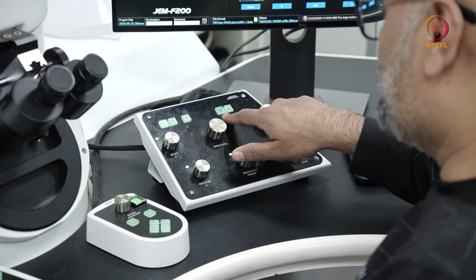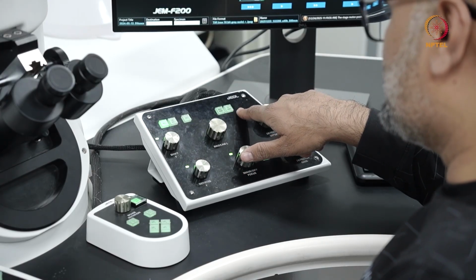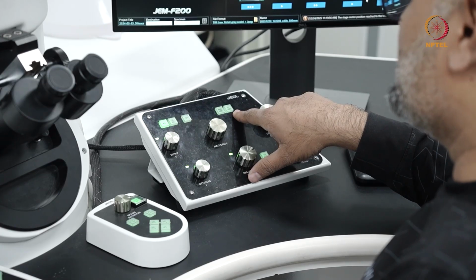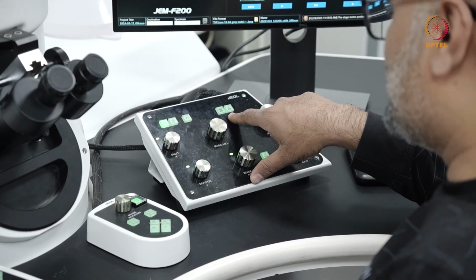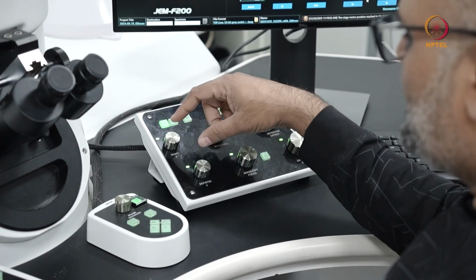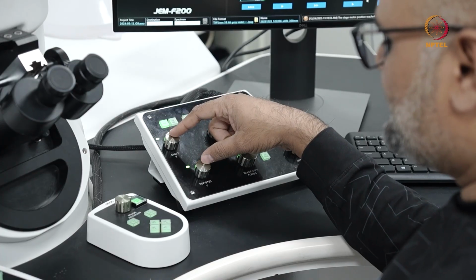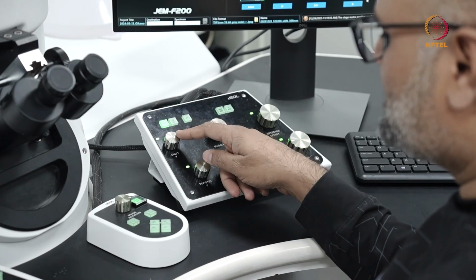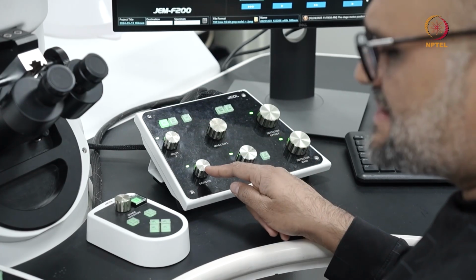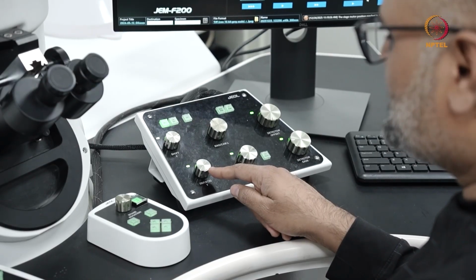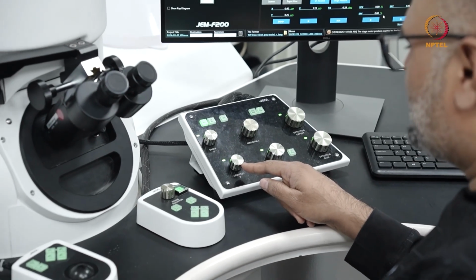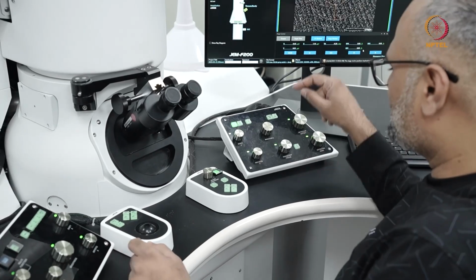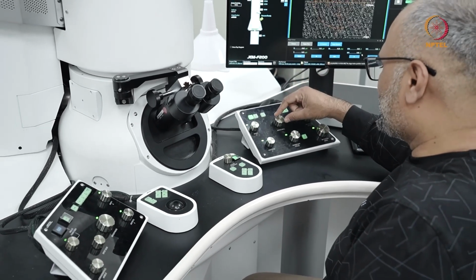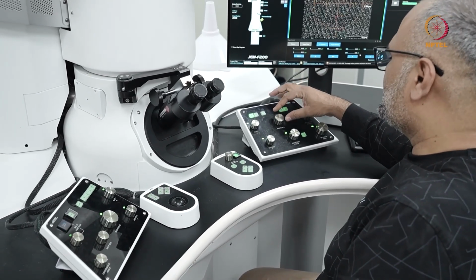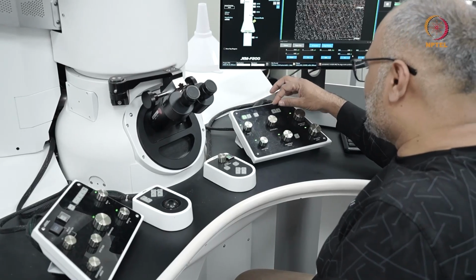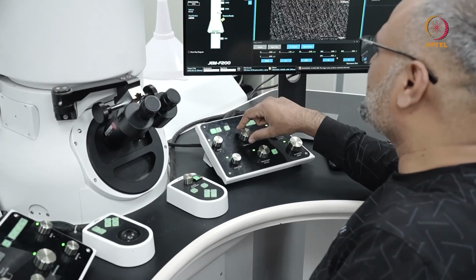You have the image wobbler and the HT wobbler here, which are used for doing some alignments when you want to do high resolution imaging. These two knobs are again shift X and shift Y, like I was mentioning a short while ago, to move the beam, and based on the functionality that is assigned, you can correct for your astigmatism or for adjusting the beam tilt or anything. Here, the magnification and the camera length, which is in imaging mode and the diffraction mode, is selected by turning this knob.